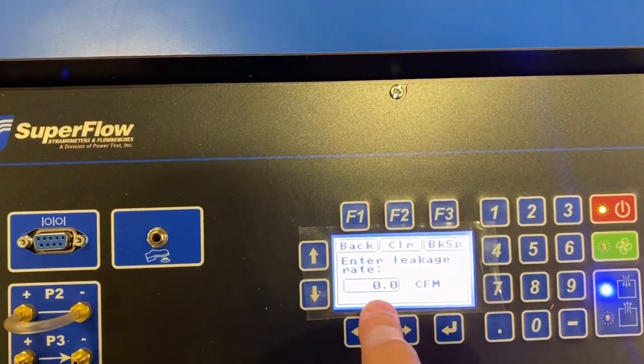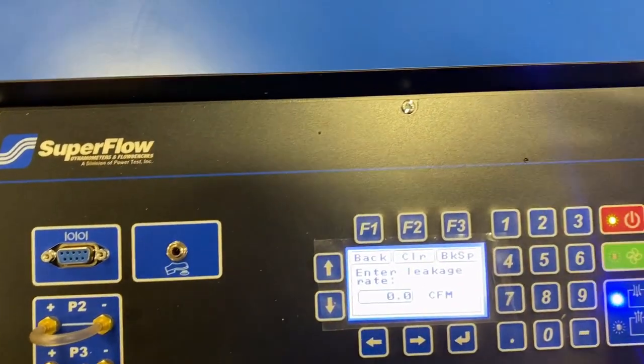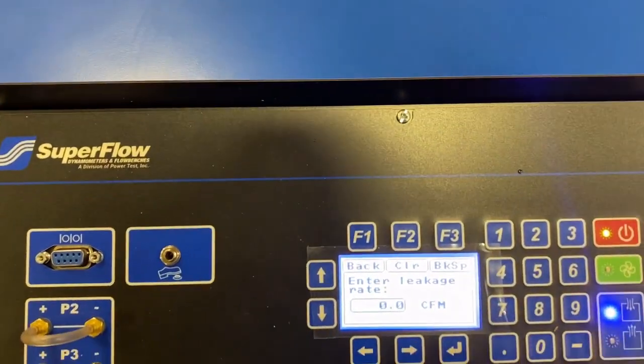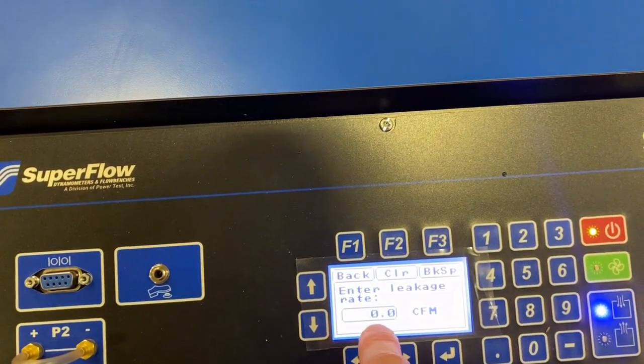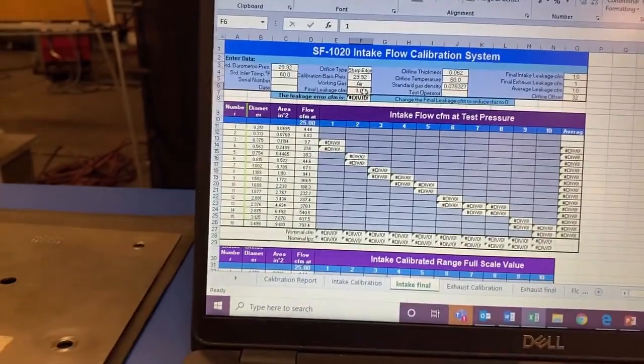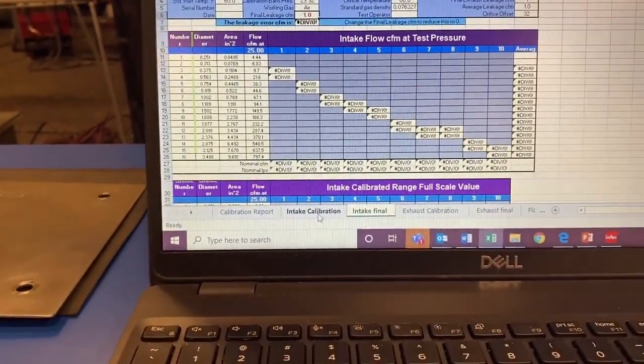The reason for that is if there is a leakage value in here, it's already subtracting the leakage away, and so you'll get a value of 0 when testing leakage. Instead, we make this 0, we test for leakage, and then we enter that value into this table here. Now we'll move on to calibration.